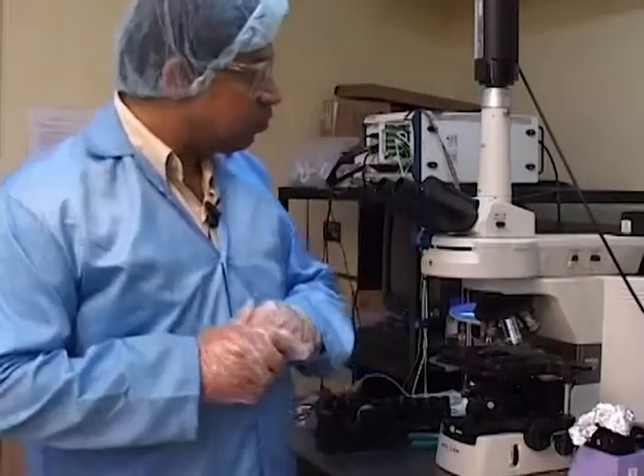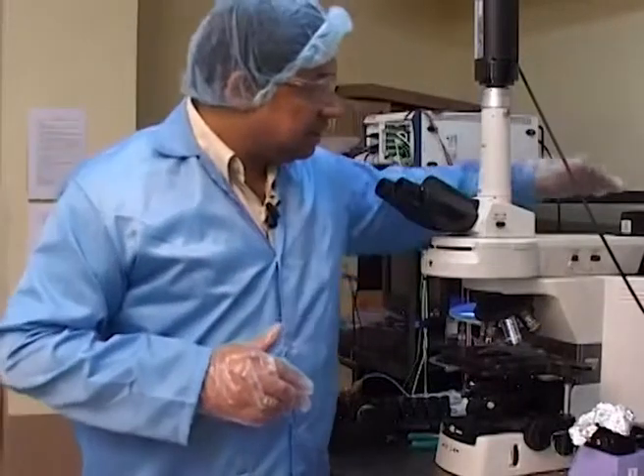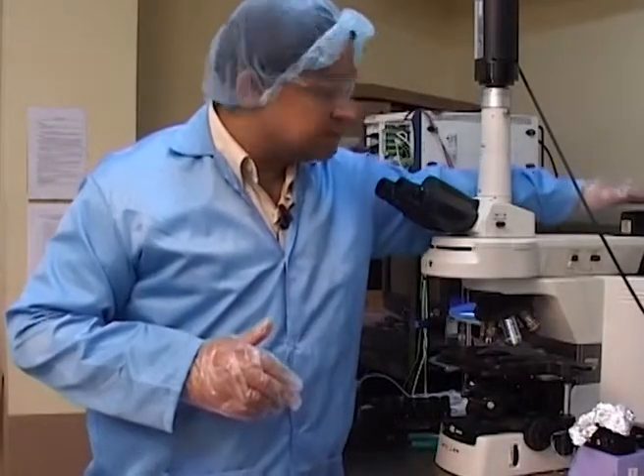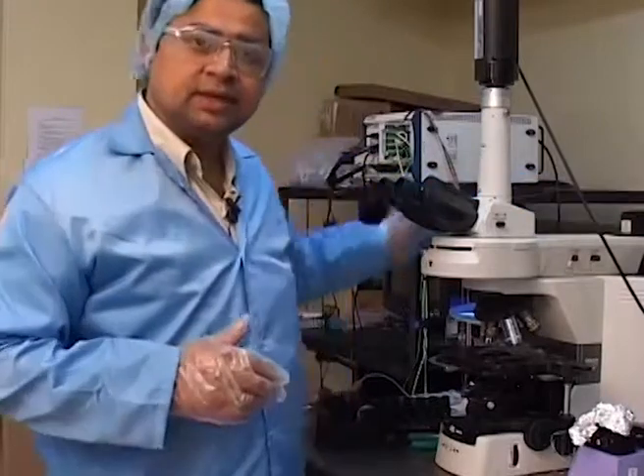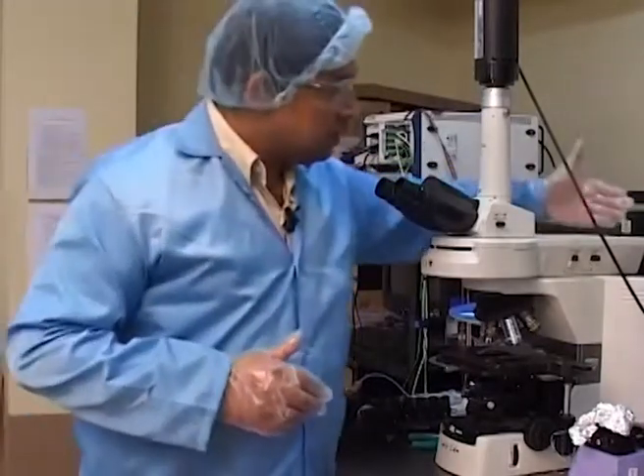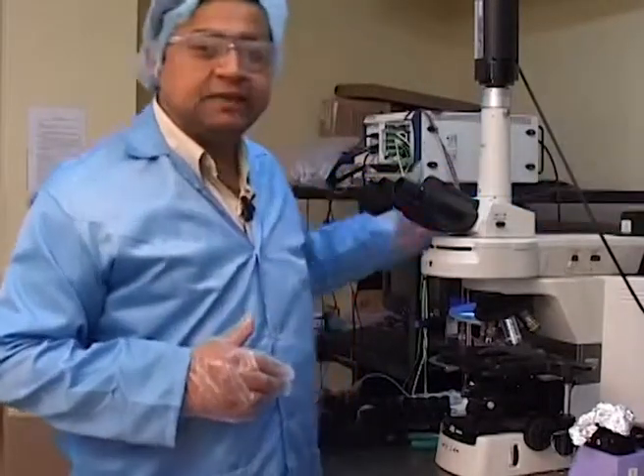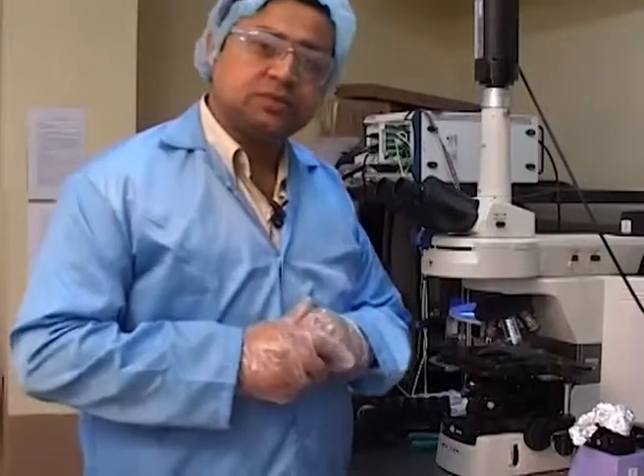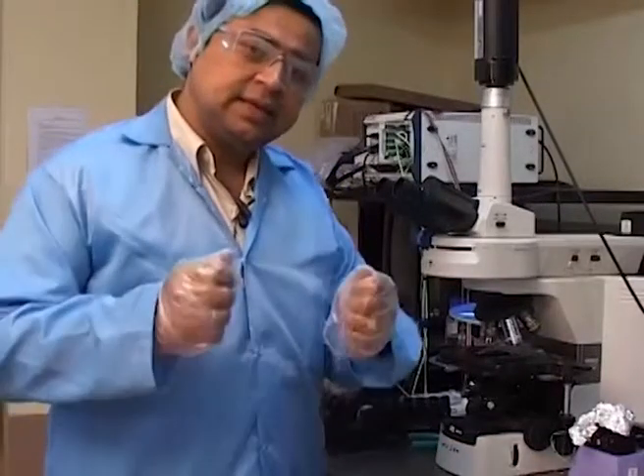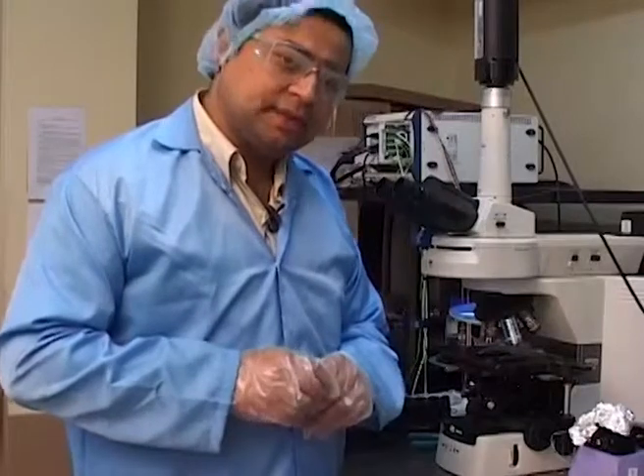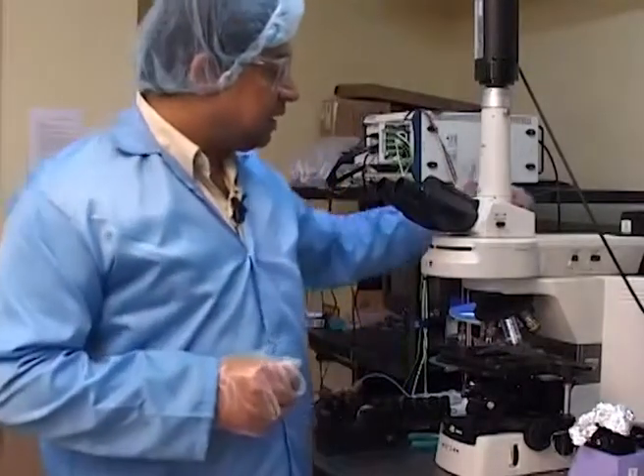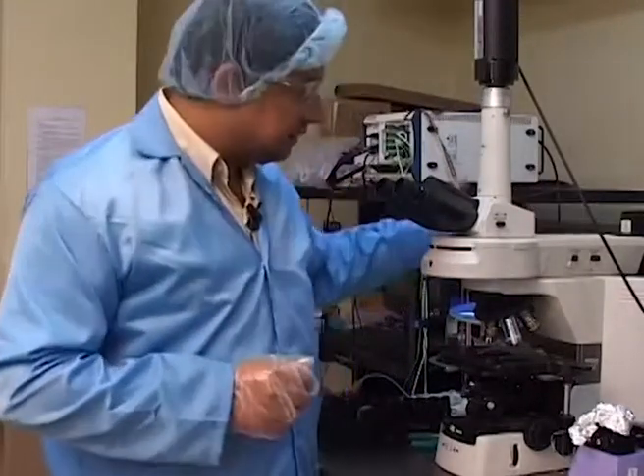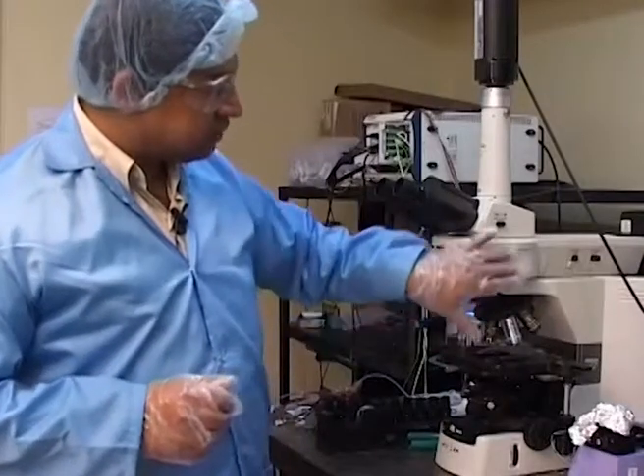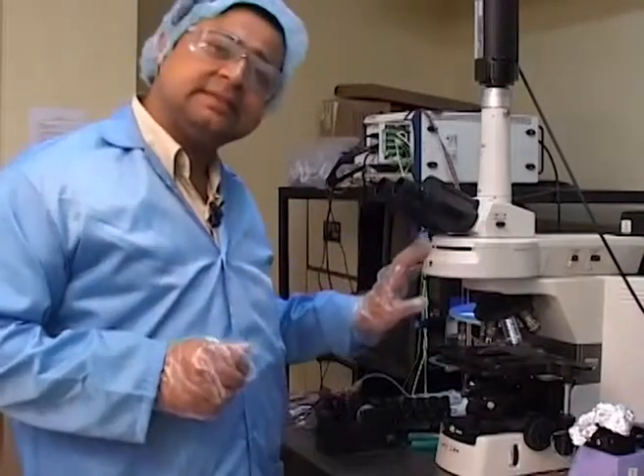The way that this microscope operates is pretty simple. You have an illumination source at the background, which is actually a UV source. It passes through a set of ND filters, neutral density filters, which would cut off the UV light into different intensities. And then finally, the cutoff light at a much lower intensity reaches this portion of the microscope, which has what you know as filter cubes.